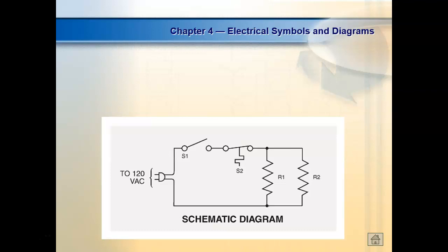So we have a problem: people waste a lot of wire because they try to wire it the way it's drawn, right? You understand? Instead of the way it would be wired in real life, to use the minimum amount of wire I can possibly use. Does that make sense? Y'all gonna do it in here. We're gonna draw L1, and somebody in here is gonna try to connect everything back up to the transformer instead of jumping it out in the circuit.